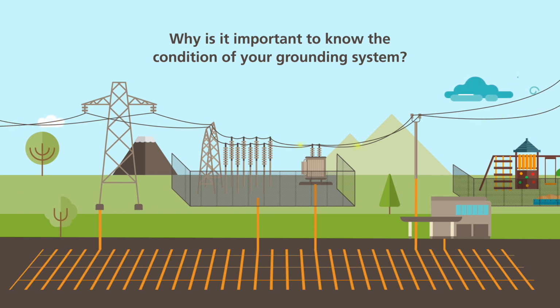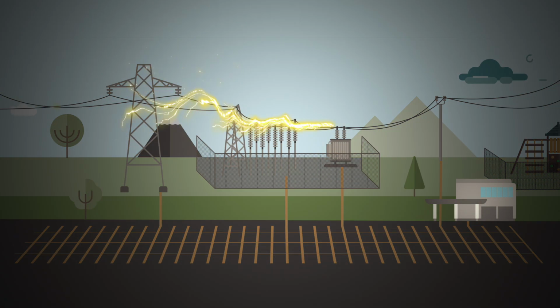Grounding systems are essential for the safe and reliable operation of electrical power systems. In the event of a ground fault, improperly designed or aged grounding systems can have a major impact. Improper grounding systems may not be able to carry the full fault currents. This may cause damage to primary assets such as transformers, as well as harm or even destroy the function of electrical devices like protection relays and communication equipment.